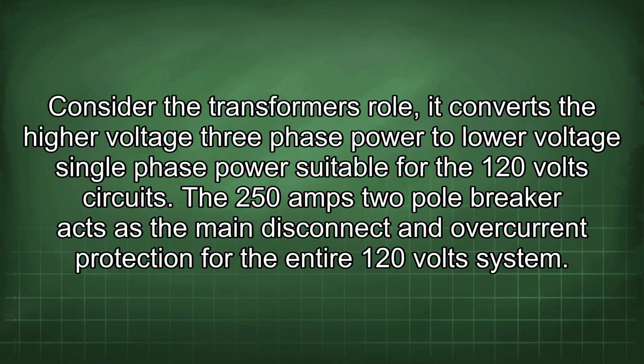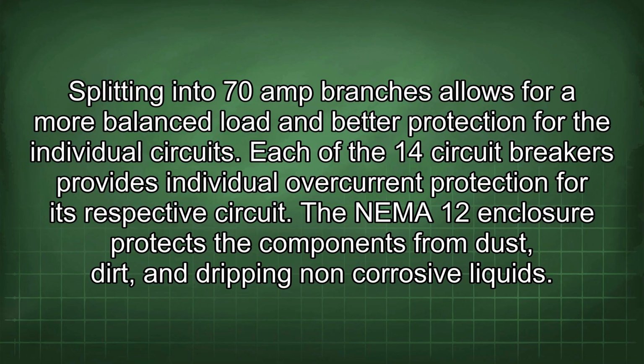Consider the transformer's role. It converts the higher voltage 3-phase power to low voltage single-phase power suitable for the 120 volt circuits. The 250 amp 2-pole breaker acts as the main disconnect and overcurrent protection for the entire 120 volt system. Splitting into 70 amp branches allows for a more balanced load and better protection for the individual circuits. Each of the 14 circuit breakers provides individual overcurrent protection for its respective circuit. The NEMA 12 enclosure protects the components from dust, dirt, and dripping non-corrosive liquids.